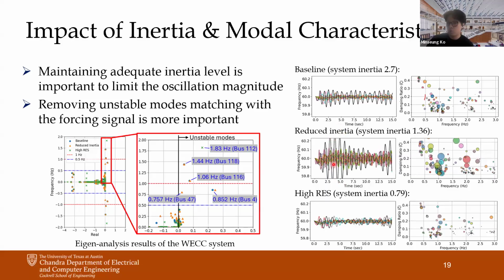But the interesting point is when we replace the synchronous generators with renewable energy sources. Since we assume the renewable energy sources are based on grid-following controllers, they do not give inertia or a large amount of damping control for frequency or oscillations. So the systemic inertia was 0.79, which was much lower than the reduced inertia case. But in terms of the oscillation magnitude, it was much lower or comparable to the baseline. This is a very interesting observation, because even if the overall system has lower inertia, it did not lead to a larger amplification of the oscillation.